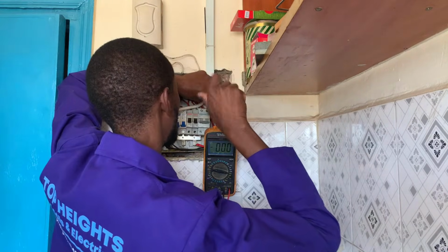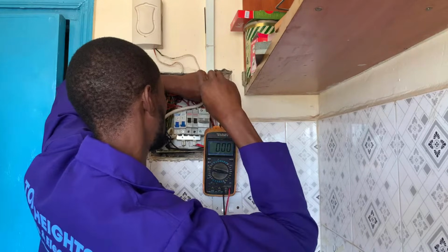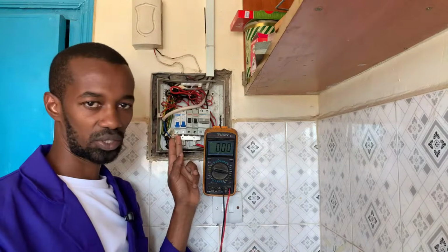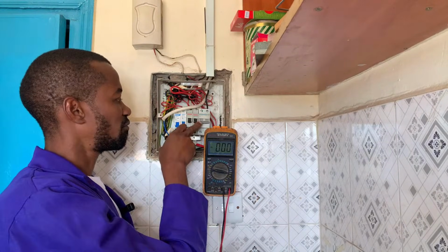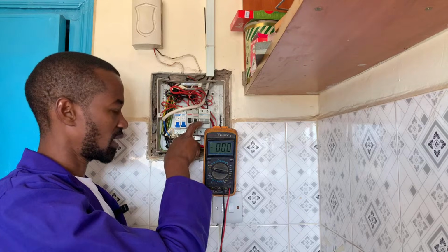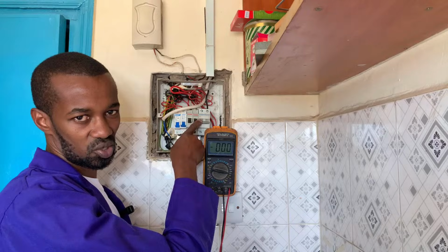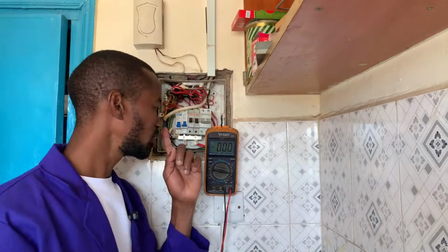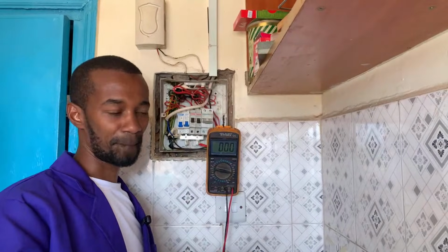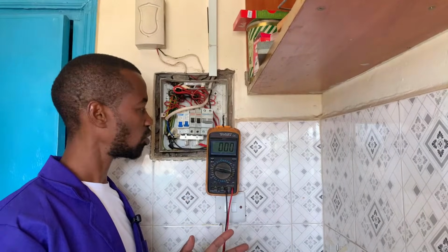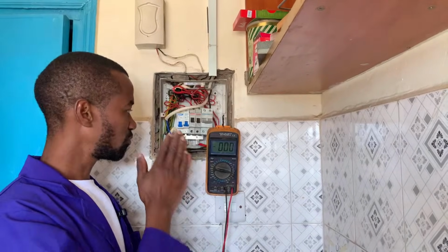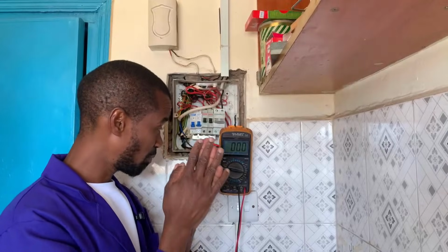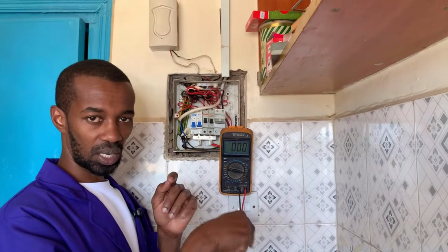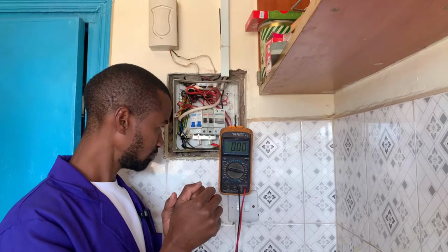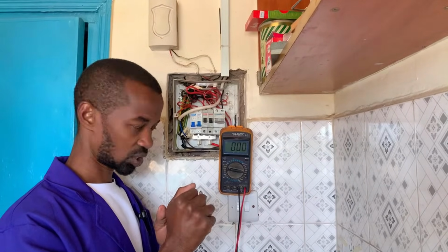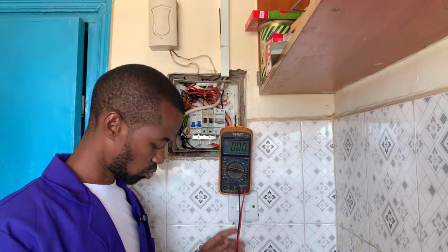Again, for such scenarios whereby you're operating a live circuit, you need to be very careful, because if there is a short circuit here, remember at the meter board we have a DP-MCB such as this one. And if there is a short circuit here while carrying out repairs, it will trip the double pole down there, shutting off current supply to the house. So even if you replace that MCB, if the double pole MCB down there is not turned on because of the overcurrent or short circuit, you will still need to sort that one out.